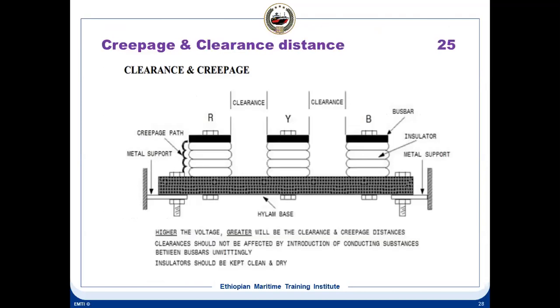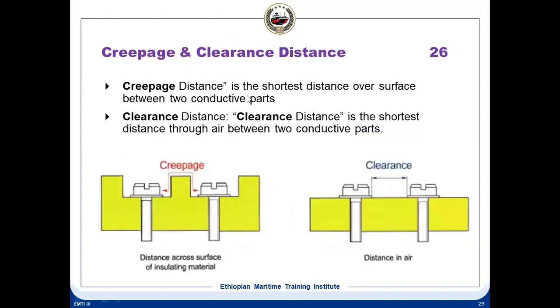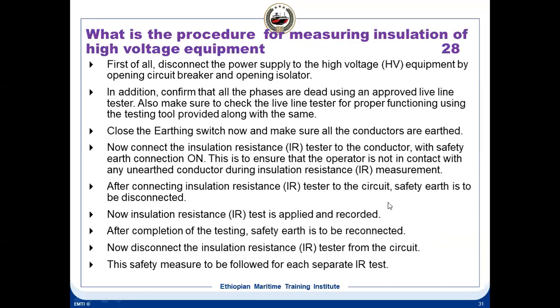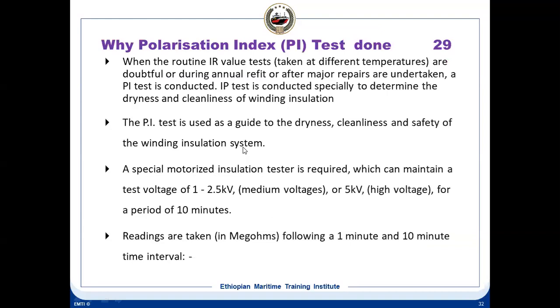Okay, what is clearance? What is creepage? Difference. Clearance means the space, the distance through air. What is the distance through air is called the clearance, and creepage means the distance along the surface between two conductive parts is the creepage, and this is the clearance. If it is asked, you can draw this diagram. Insulation test. What is the procedure for insulation test of high voltage equipment? How do you proceed? If you want to do an IR test, what are the procedures? What is polarization index test? Why do you do polarization index test? If the values are less, then what is the next course of action?